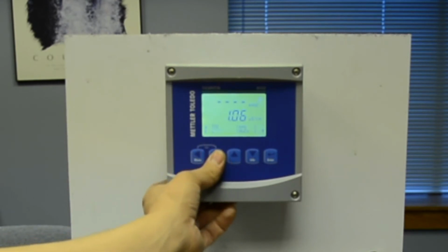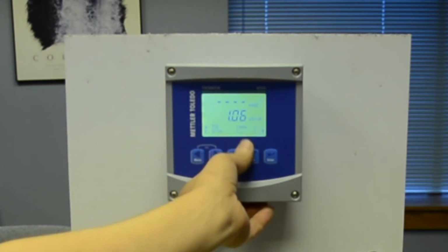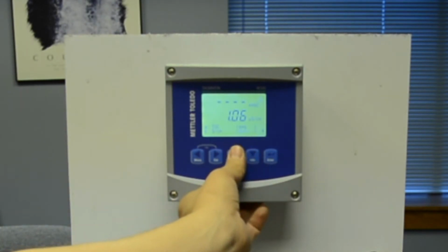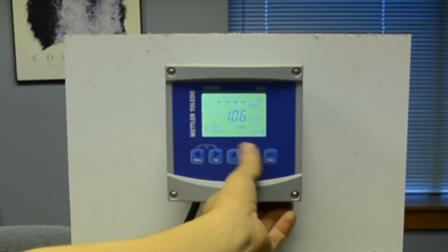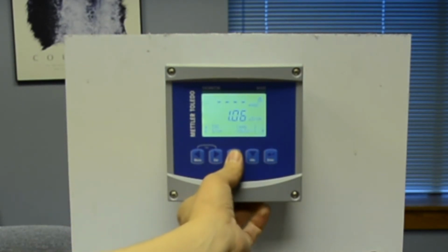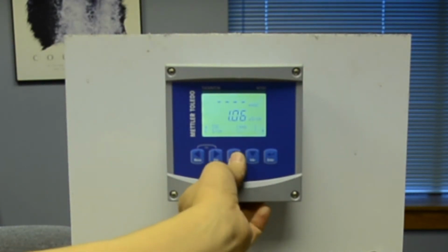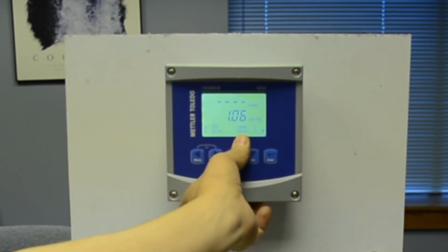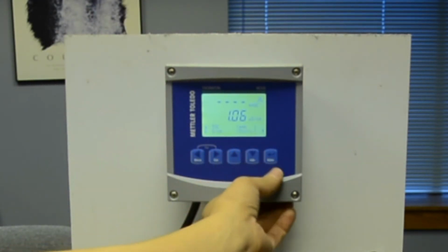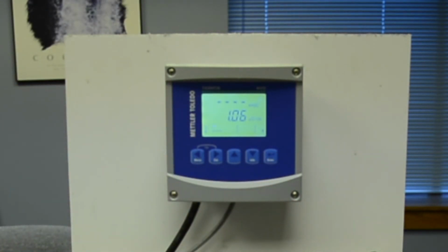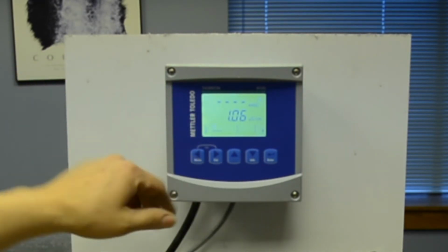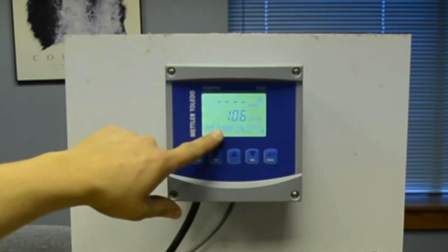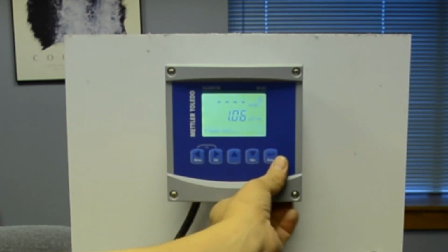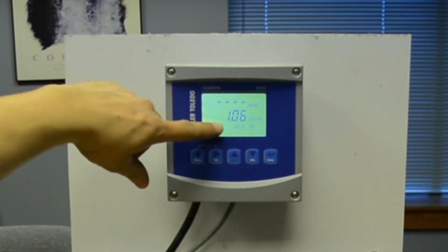To prevent that from happening, because you want to be reading it in microsiemens, we're going to scroll over to auto and then hit the up or down arrows to readjust it to whatever you want it to be, micro or milli units. Back to auto. We want it to be in micro, so it's reading microsiemens. Then hit enter. Now it will give you channel C and channel D. You don't need to adjust these channels because we only need to see that one reading on either channel B, C, or D, and it doesn't matter which channel you set it up on. Hit enter again, and it's going to ask you if you want to save your changes and exit. Press enter for yes, and it'll save your changes and exit, and now you'll be reading conductivity here.